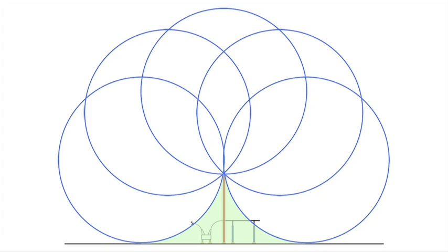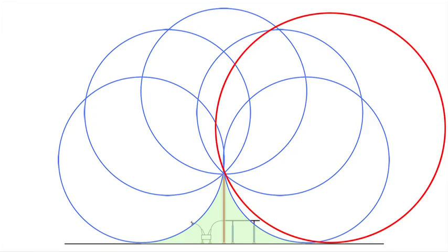All right, so going back to this example, we see that a certain stroke current that results in a strike distance of this blue circle leaves this area unprotected. But if the stroke current was just a little bit larger, as illustrated by this red circle, that area would actually be protected.